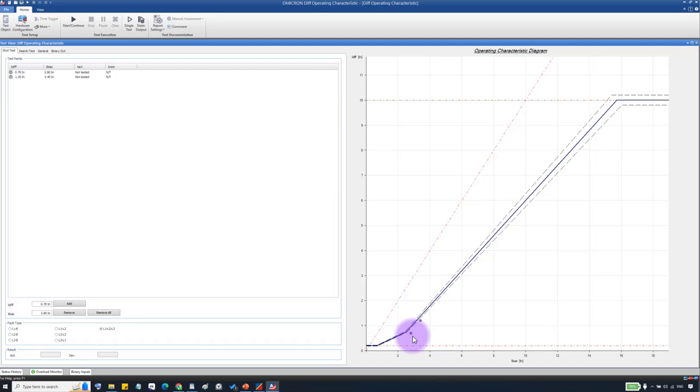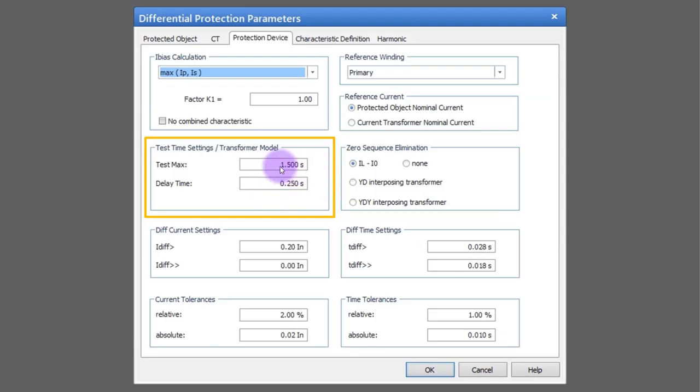It is very long. And not only this, but maybe the other functions will also be picked up. For instance, overcurrent. If you inject these values to the relay, maybe the other function will also pick up and trip. So that is another problem. So we should keep it optimal. 1.5 is okay.